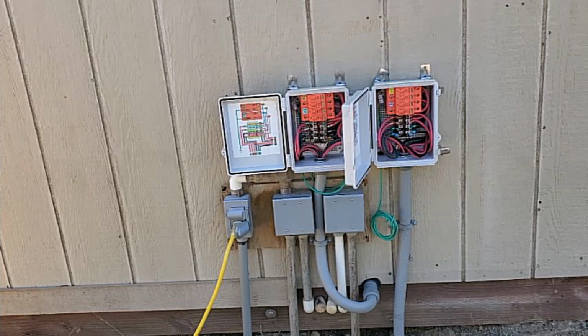On the left-hand side, you'll find the input terminals for arrays 1 and 2. The right-hand side is designated for arrays 3 and 4. To maintain clean, isolated wiring paths, I used Dinkle DK6N DIN rail terminal blocks, which provide solid, reliable connections while keeping each array circuit separate and organized. For additional protection, I installed 2 1000-volt DC solar PV lightning arresters, safeguarding the system from voltage spikes due to nearby lightning strikes or electrical surges.